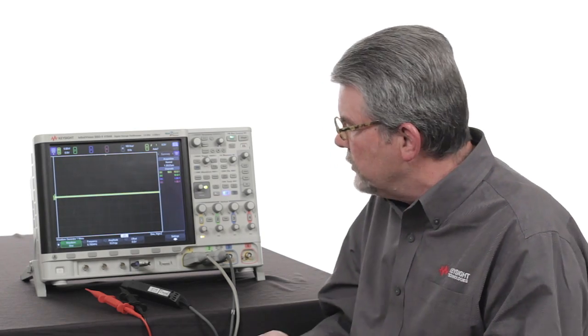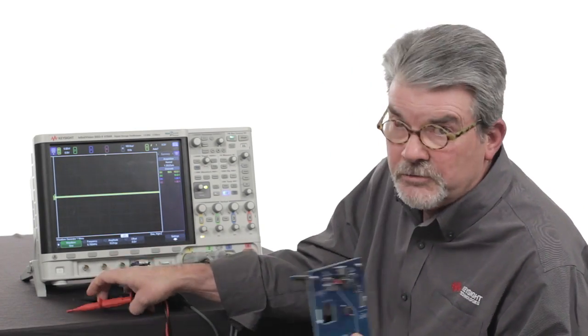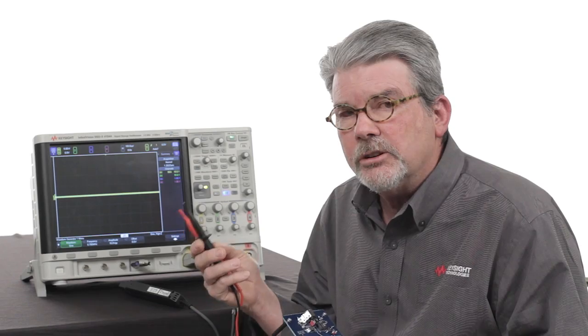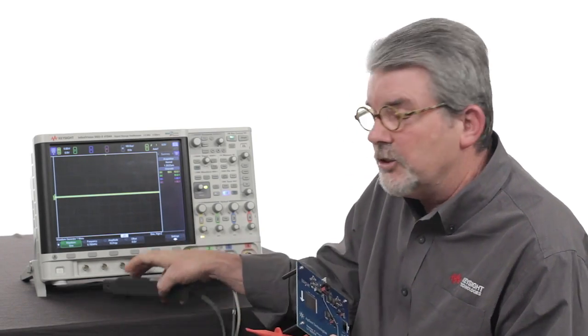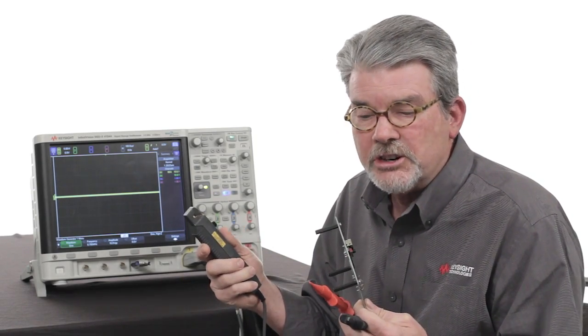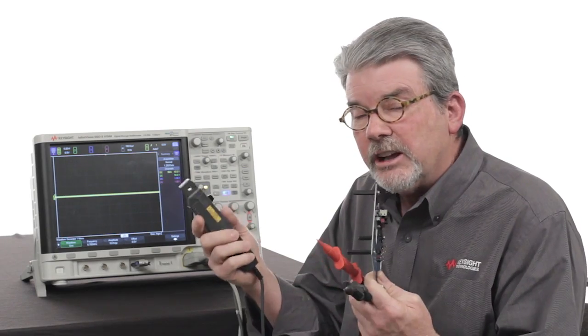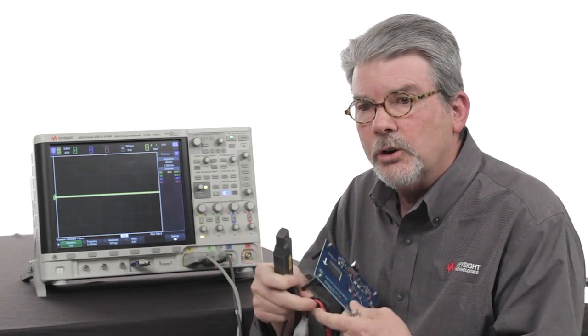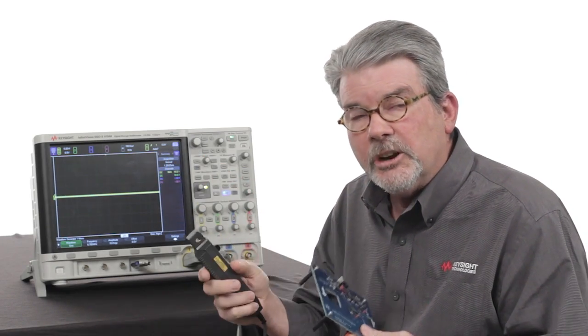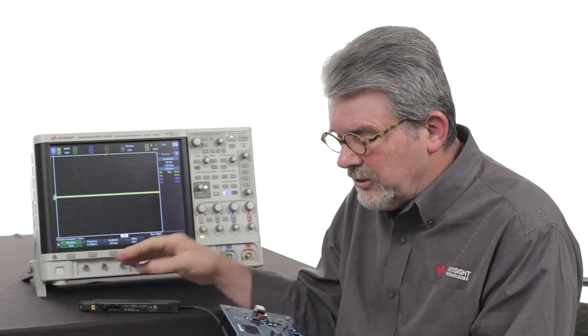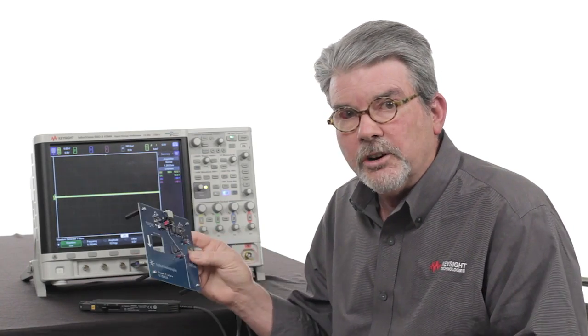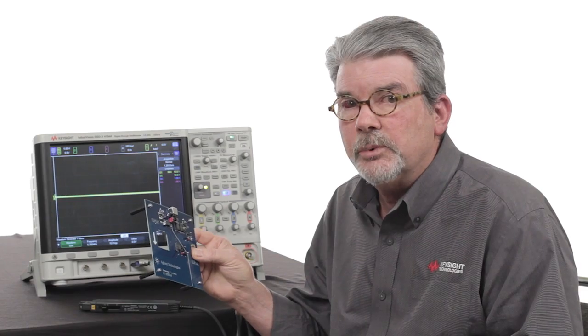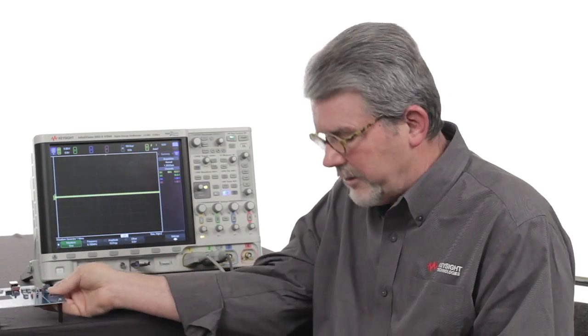Now the most important thing you need to do when making either power or efficiency measurements is you must first de-skew your probes. You're typically using, or you should be using, a differential active voltage probe as well as a current probe in order to measure power. There can be a delay difference between the voltage probe and the current probe, and that must be de-skewed. Keysight offers a de-skew board where you can automatically de-skew your probes, but I have something better.